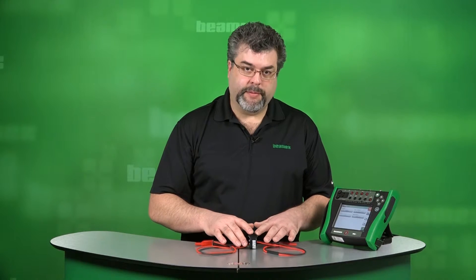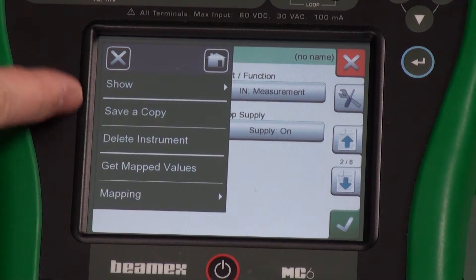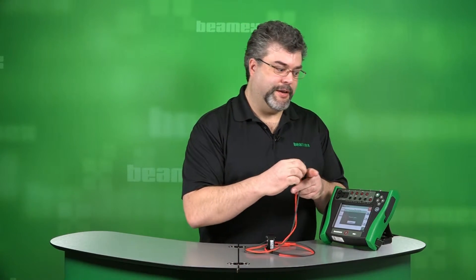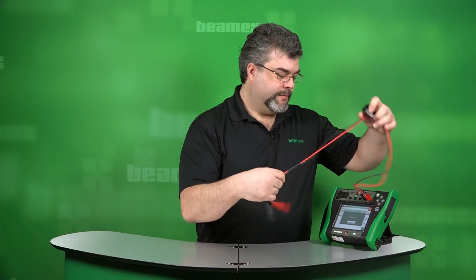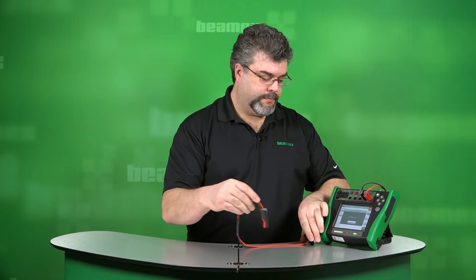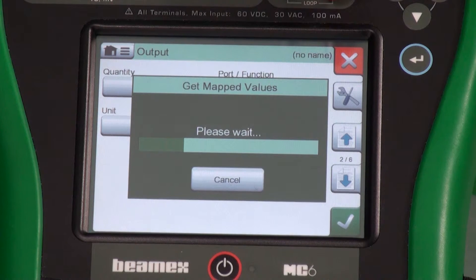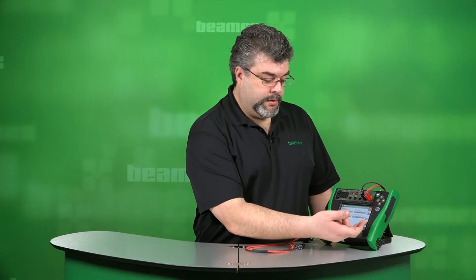But we can also pull the parameters from the device if it is a smart device. This happens to be a HART-based temperature transmitter, but we can also do this with a Foundation Fieldbus or a Profibus. That option is called get mapped values. This starts up the communicator, and in this case we'll actually have to plug it in. So we're starting up the HART communicator and this will pull in the values. You can see the activity right there. As we go down, we can see that it is output current.